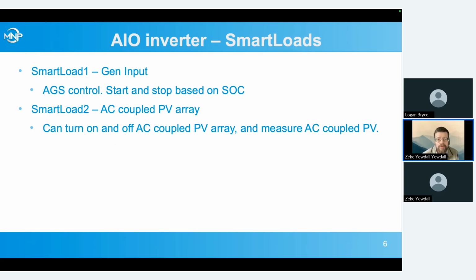Smart load 1, our generator input, has AGS control. We can start and stop the generator based on state of charge. If you're in open loop on voltage mode, say with a lead acid battery or a different lithium battery that's not communicating with the inverter, then you'll have voltage base for your AGS control.